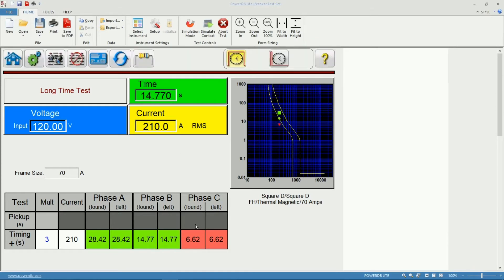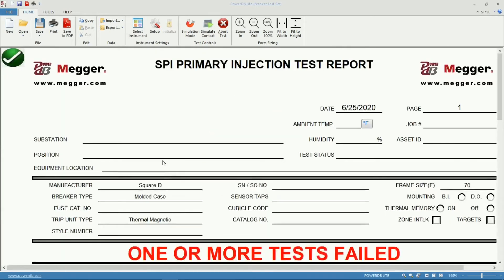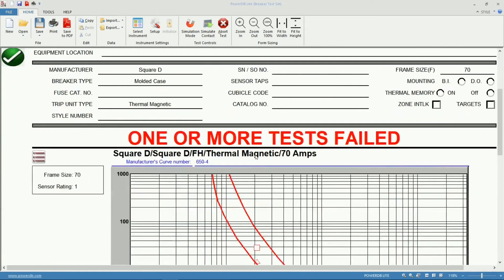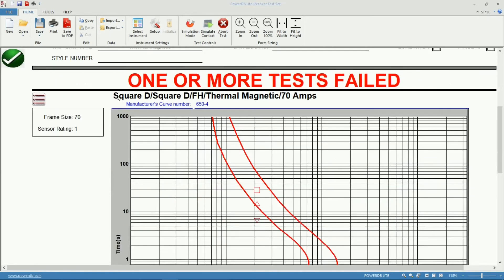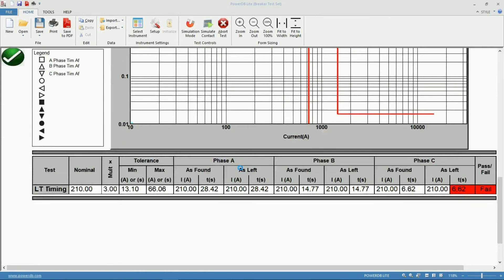In this case I'm going to simulate a trip outside the limits of the curve. So now one of our phases failed, so let's look at how that's displayed in my report. You can see big and prominent red letters, the report is indicating that one or more of the measurements failed. I see the plottings in the curve as well as the numerical values in my results table at the bottom of the page.